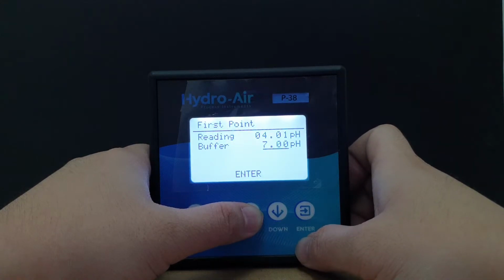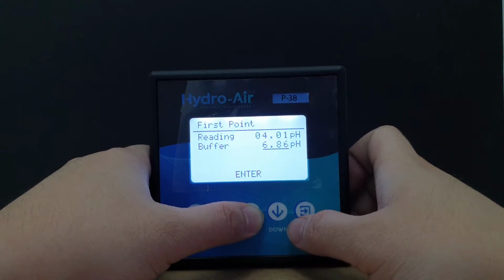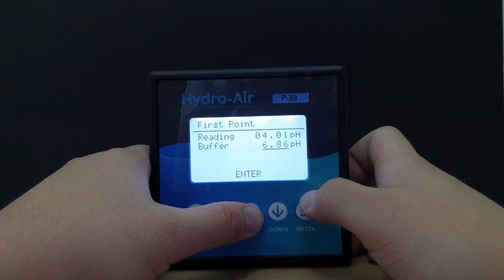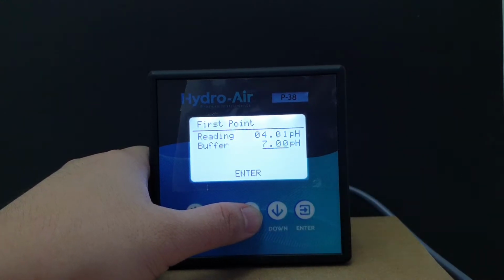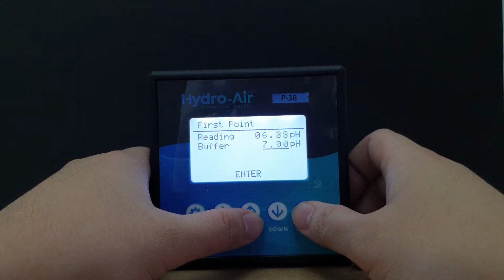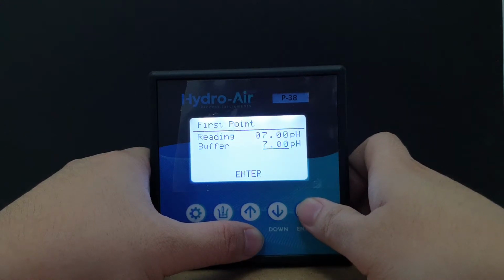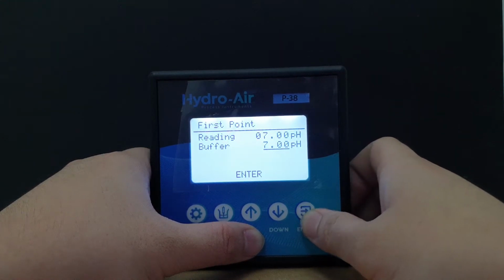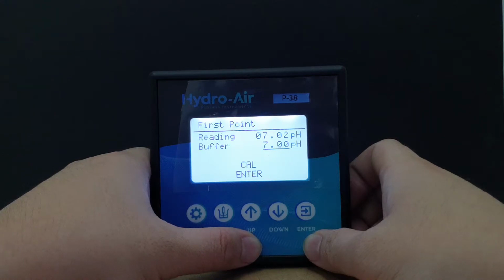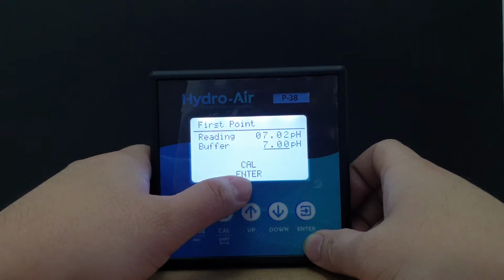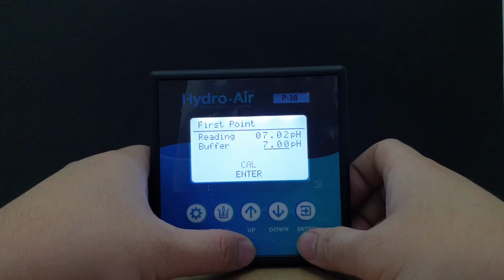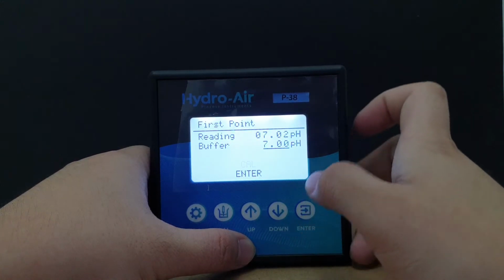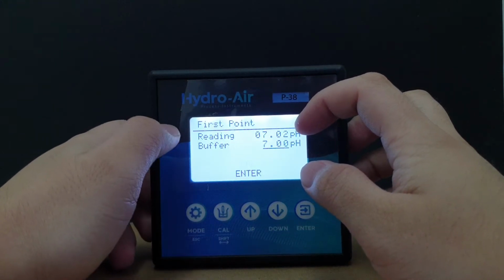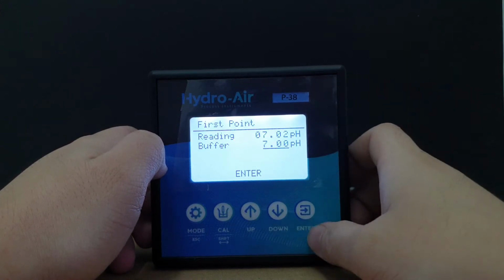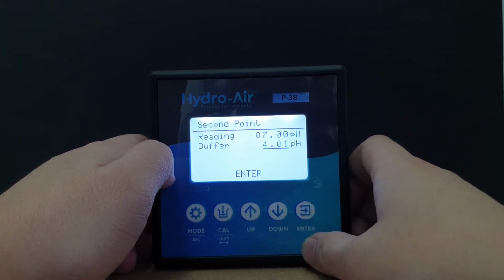The first is the 7.00 and 6.86. Right here, we are going to simulate a 7.00 pH and we're going to press enter. Now you see that the cal is blinking, which means that calibration is in progress. So when you see that the reading has stabilized, you are going to press enter to lock in.